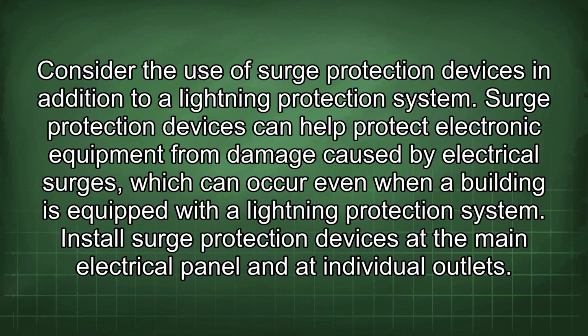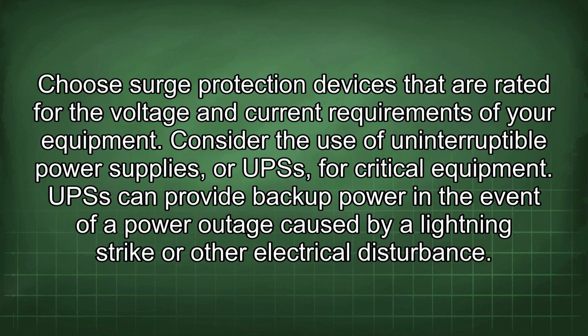Consider the use of surge protection devices in addition to a lightning protection system. Surge protection devices can help protect electronic equipment from damage caused by electrical surges, which can occur even when a building is equipped with a lightning protection system. Install surge protection devices at the main electrical panel and at individual outlets. Choose surge protection devices that are rated for the voltage and current requirements of your equipment.